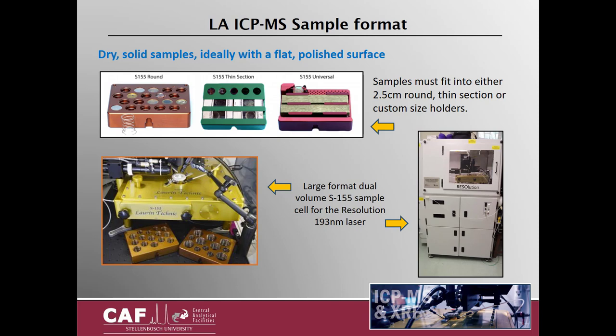The sample format for the laser ICP analysis is dry solid samples, ideally with a flat polished surface. The sample must fit into either 2.5 cm round, thin section, or custom size sample holders, which then fit into our large format cell as part of our resolution instrument.